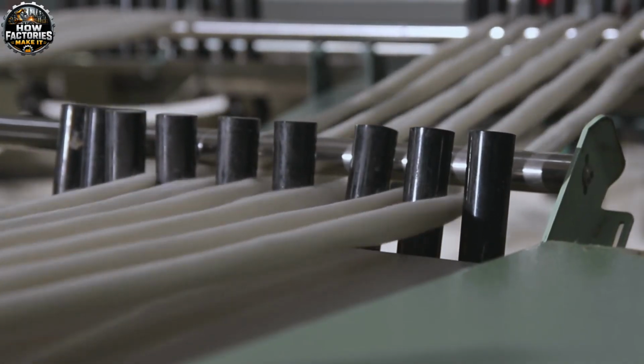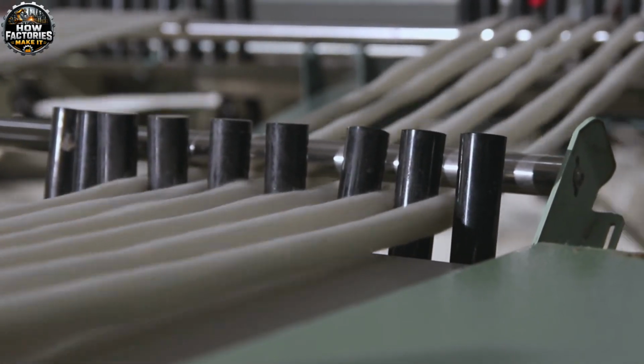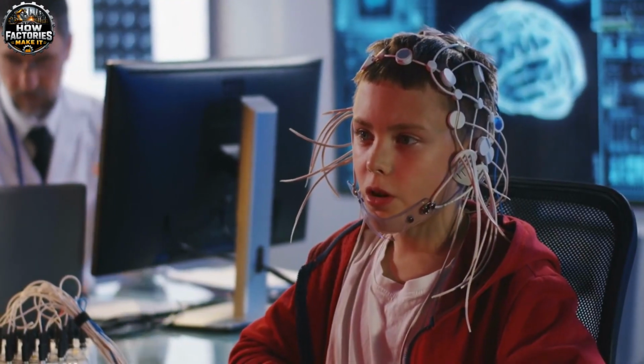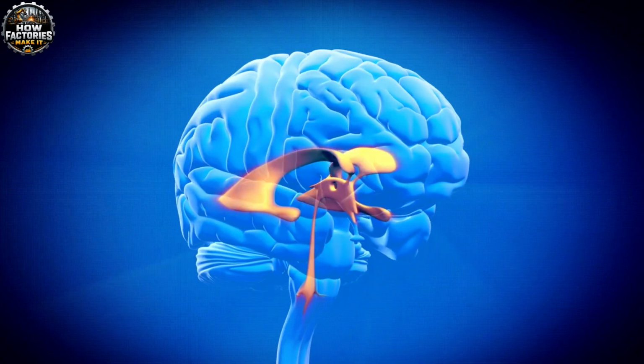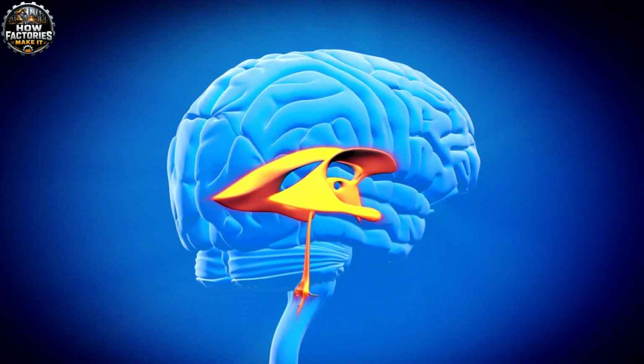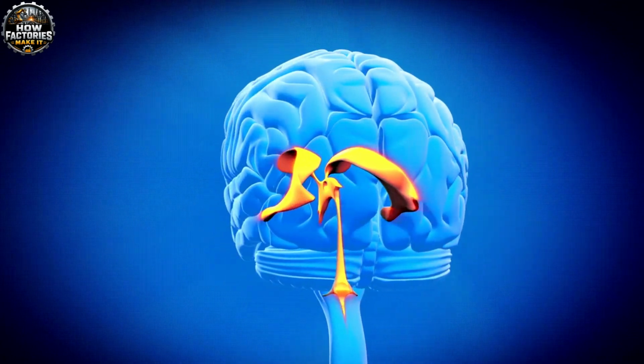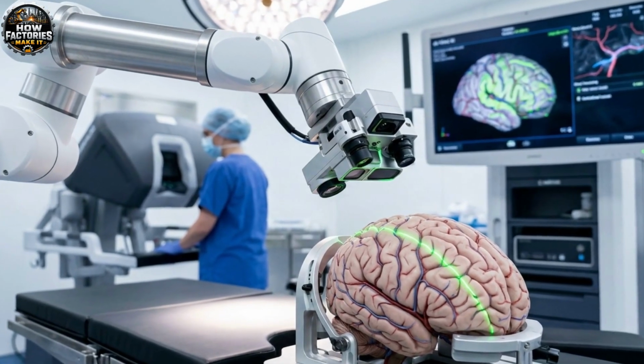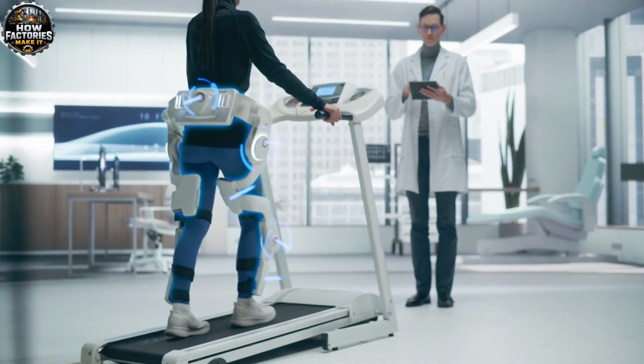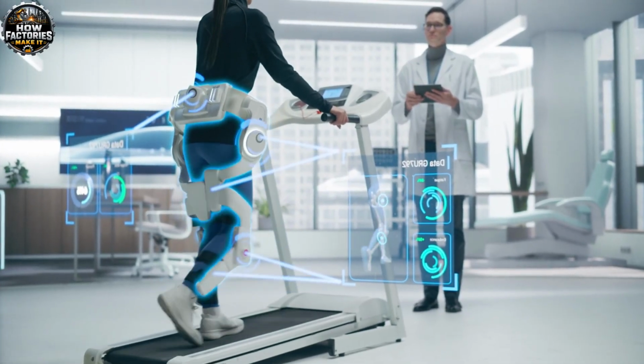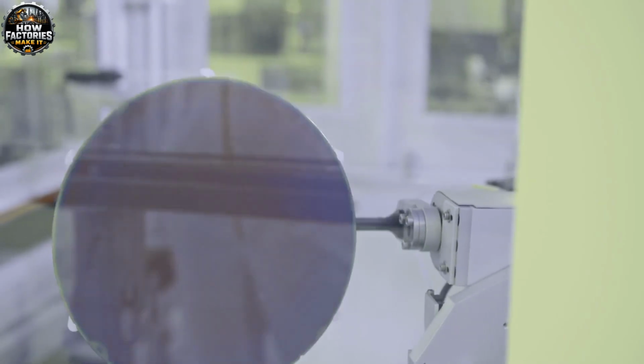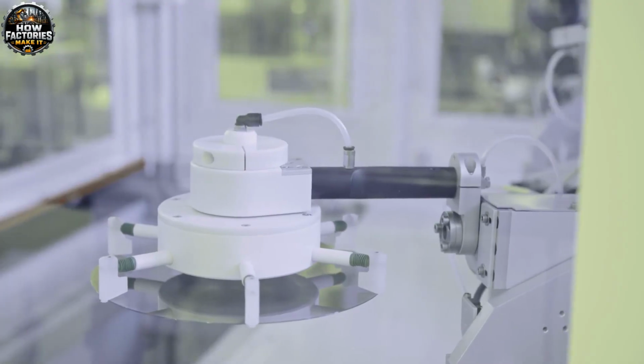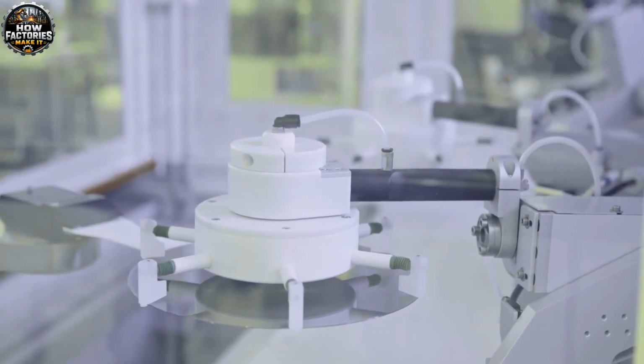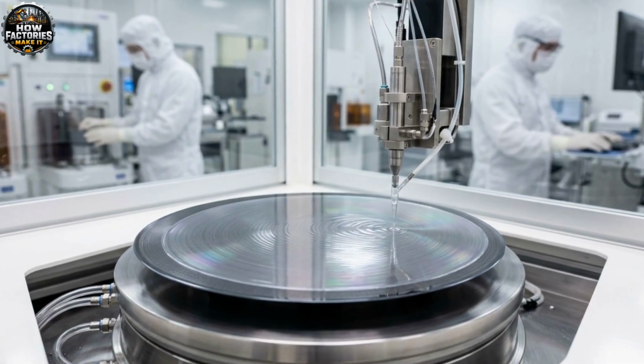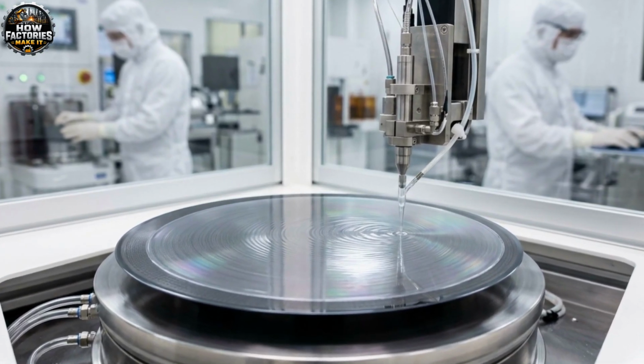The neural threads are among the most difficult components to manufacture. Traditional brain electrodes are often relatively stiff, but brain tissue is extremely soft and moves slightly with breathing, blood circulation, and normal body motion. A rigid implant can create mechanical stress where the device meets the tissue. Neuralink's approach uses narrow polymer threads designed to be much more flexible. Production begins on another clean wafer, but this wafer serves as a temporary manufacturing platform rather than becoming part of the final implant. A thin layer of polyimide or another biocompatible polymer is deposited across the surface.